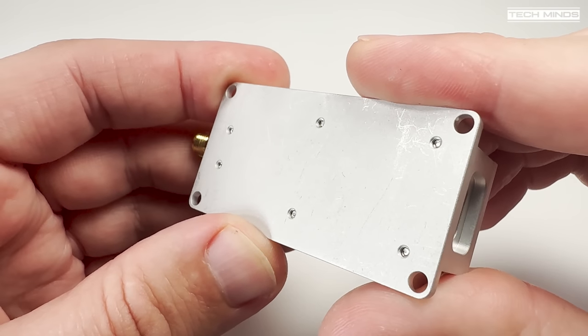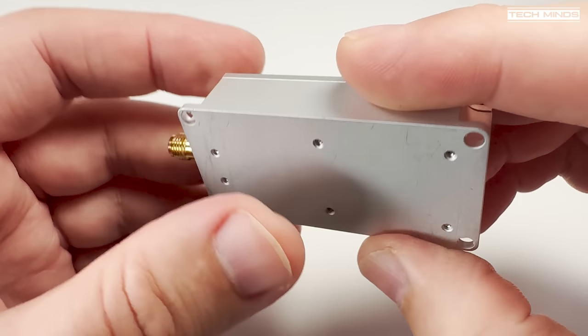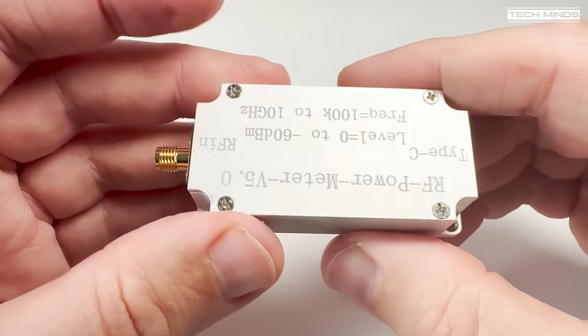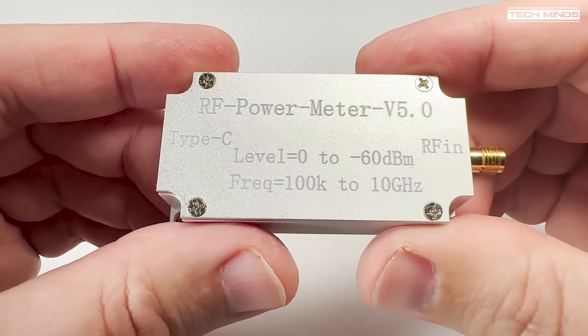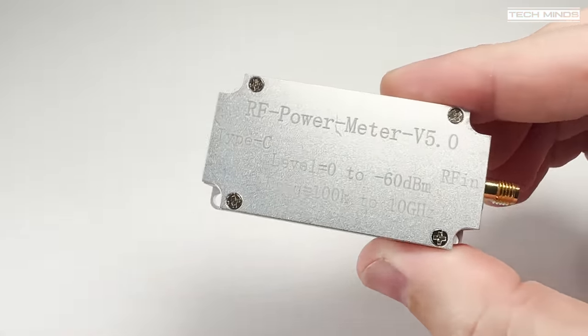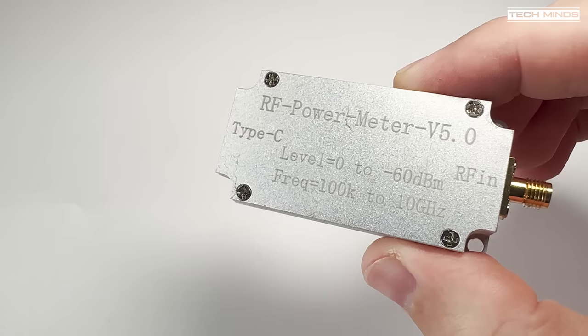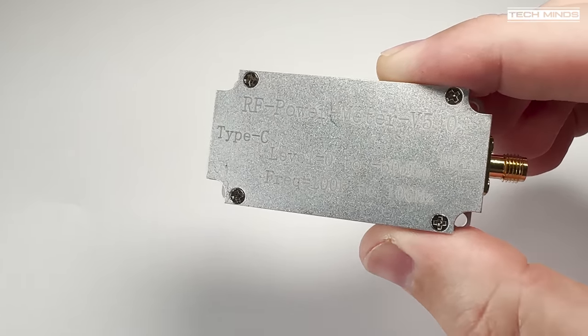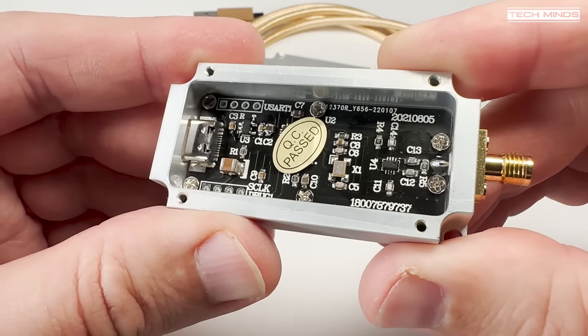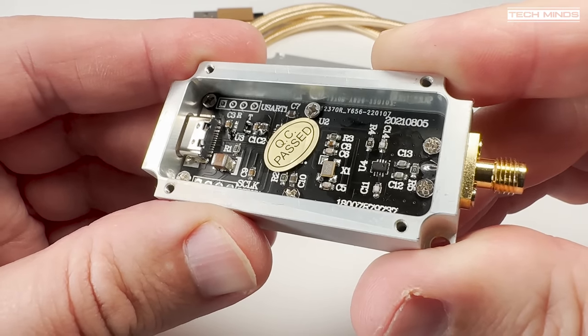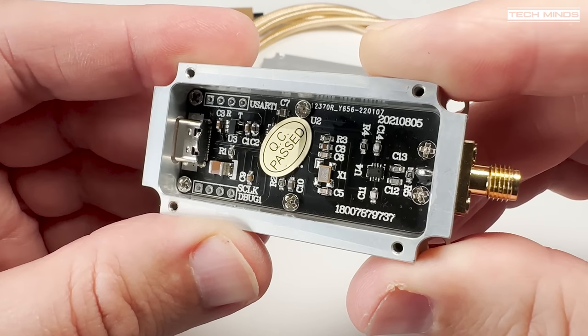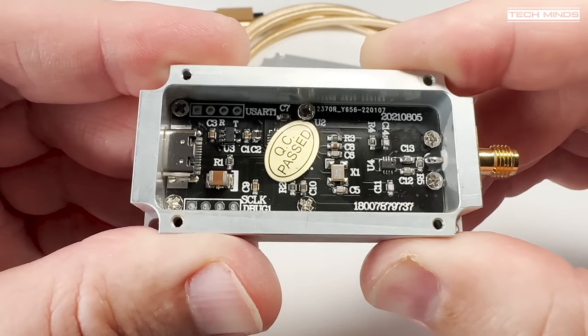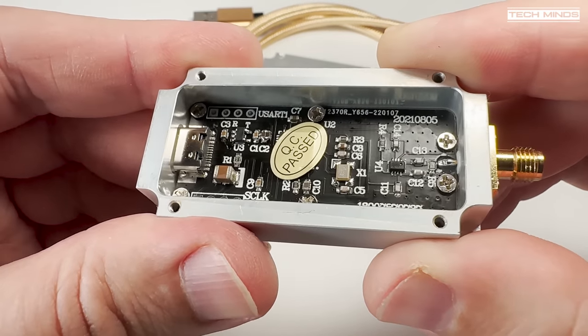Remember that this device has a maximum input of 0 dBm so it's advisable to always use an attenuator between the power meter and your device under test. The size of the attenuator will be determined by how much power your transmitter is emitting. An offset can be entered into the software which we'll look at shortly.